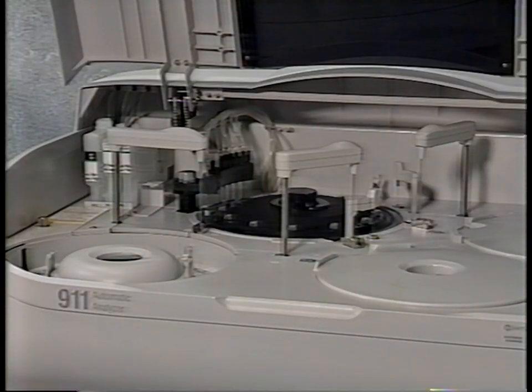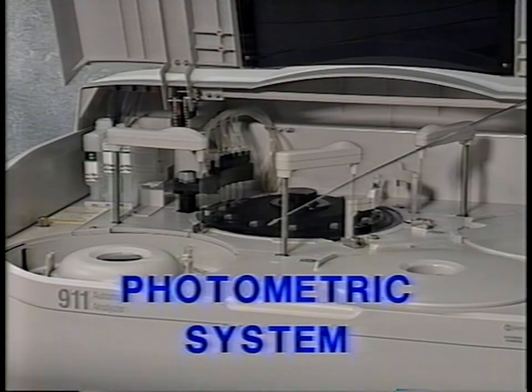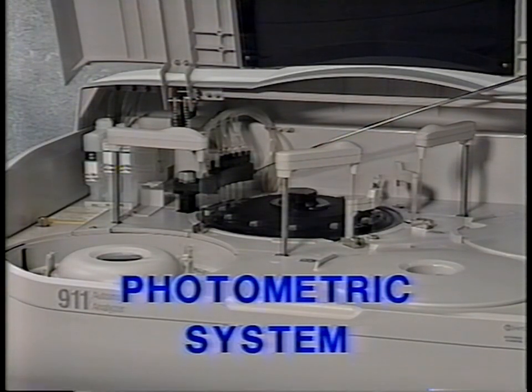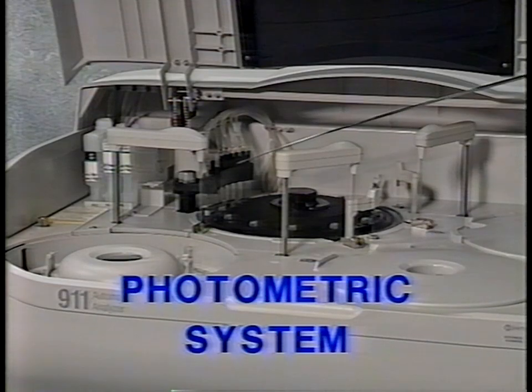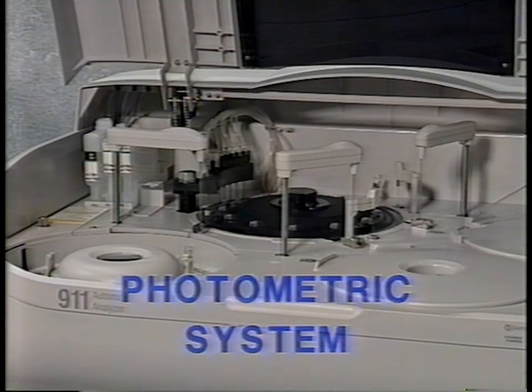The photometric system consists of the reaction cells on the reaction disc, the sample probe here, the two reagent probes, the stirring paddles, the photometer, which is located underneath here, the cell rinse unit, the reaction bath, which is positioned beneath the reaction disc, and the reagents, which are stored in refrigerated compartments here.